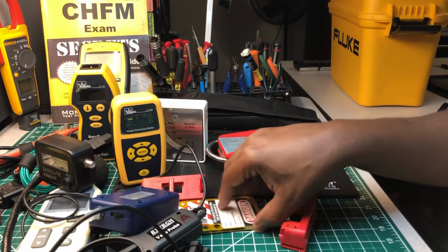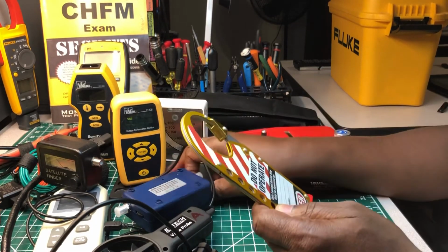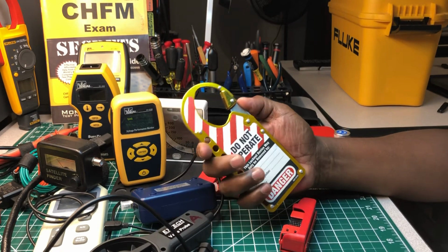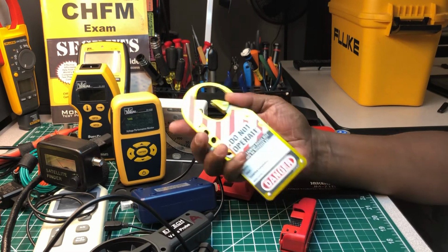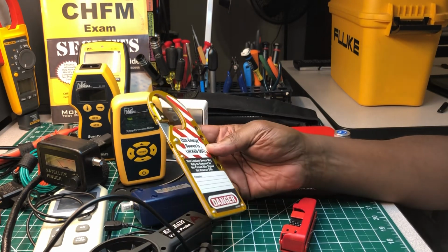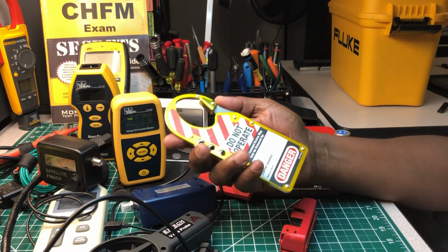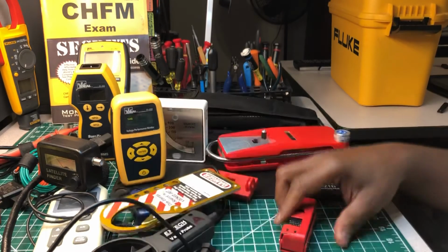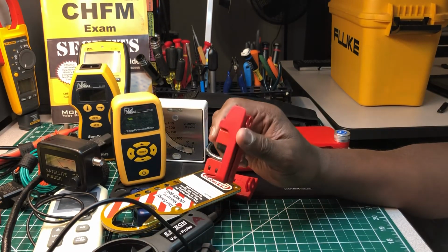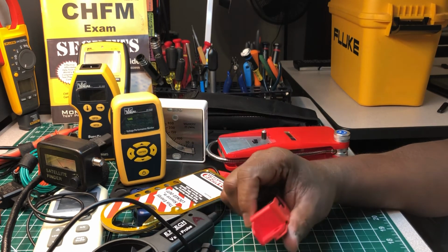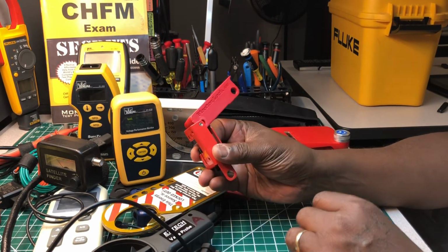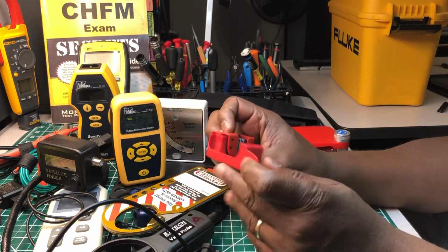If you're an electrician or any technician, whatever you do, you must have lockout tagout. You've got to have it. This is mine right here, and I still use it to this day. When I'm working on panels, residential or commercial, I still use this if needed. If I can't lock the whole panel out because they need the rest of those breakers on, for the breaker that I'm working on I'll use this single breaker lockout. It's by Master Lock, number 491B.